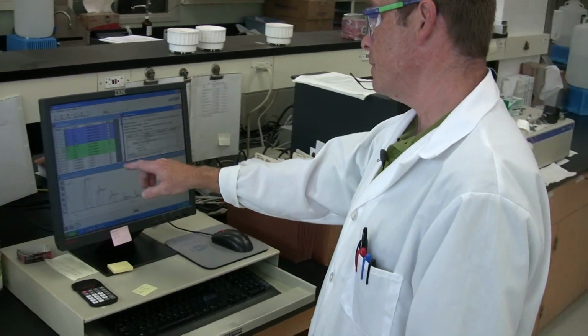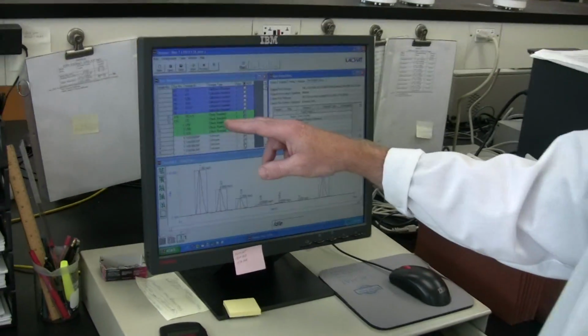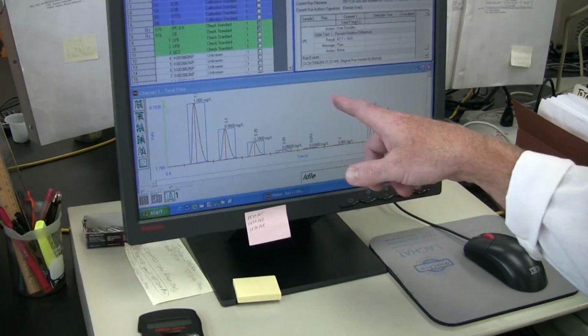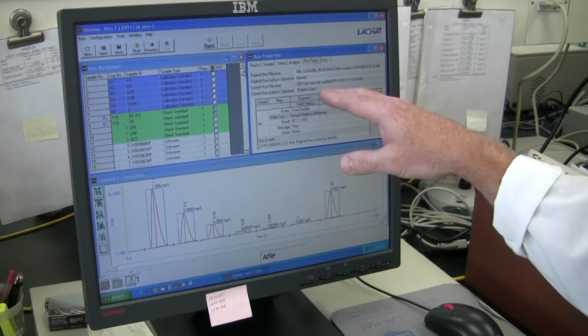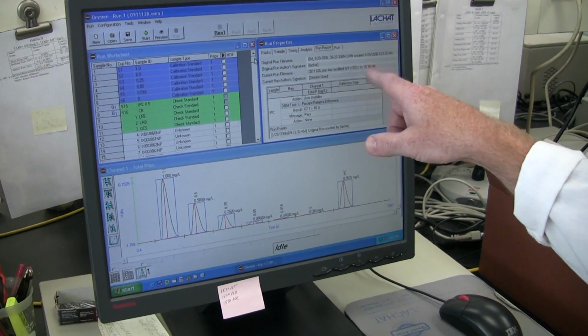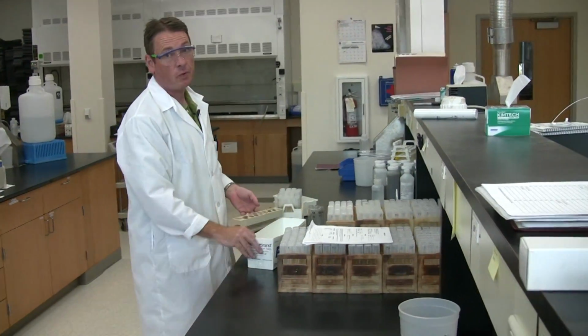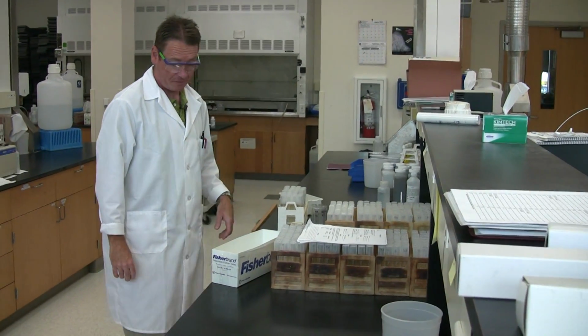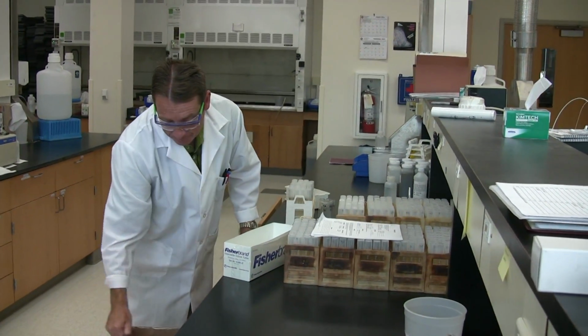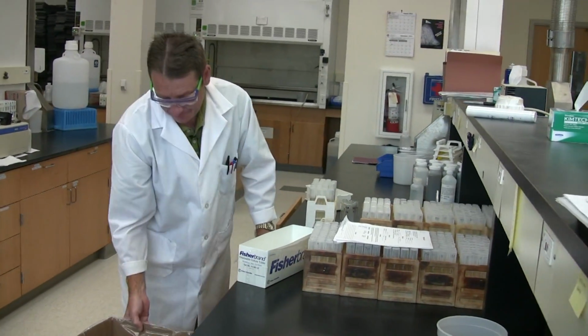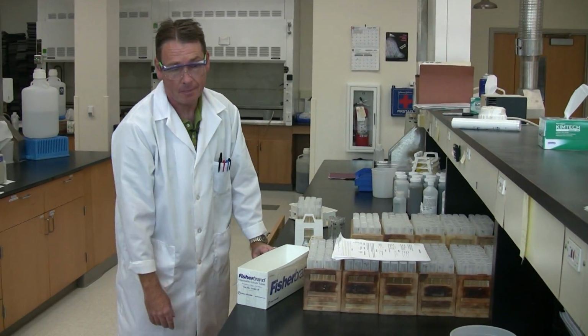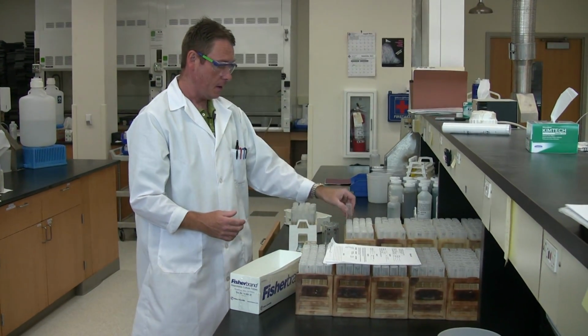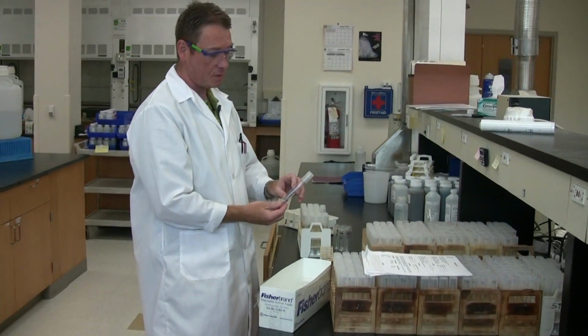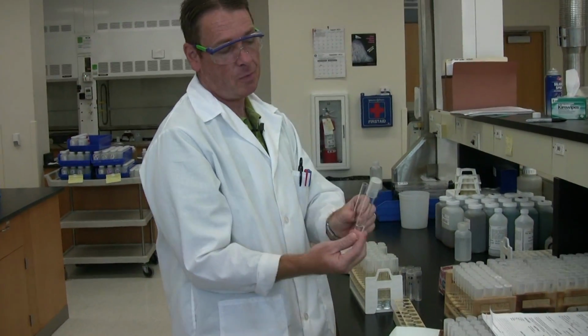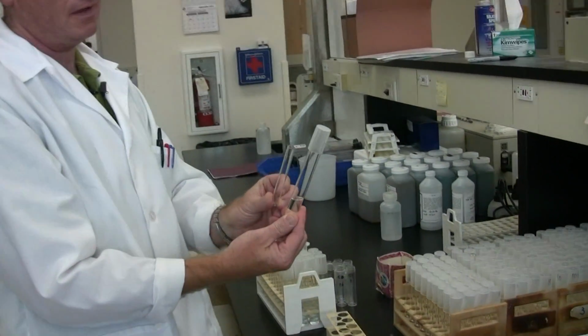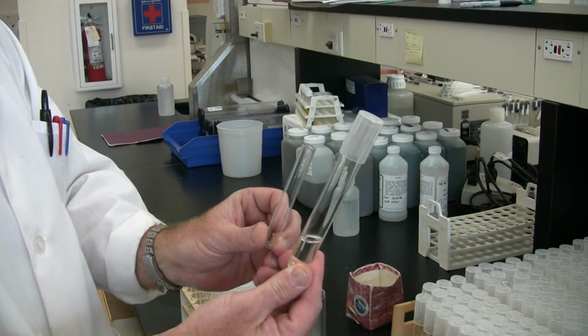We have three basic windows: what's on the sampler, what's going on past the detector here, and then this is actually the results spitting out in this report window. Basically, I have to pour these into smaller tubes so they'll all fit on the sampler. We have to use a larger tube to do the digestion because it just needs more room for expansion, and if it bubbles at all. But I'll be pouring it into a much smaller test tube to fit on the instrument so I can fit those 186 test tubes in a small place.